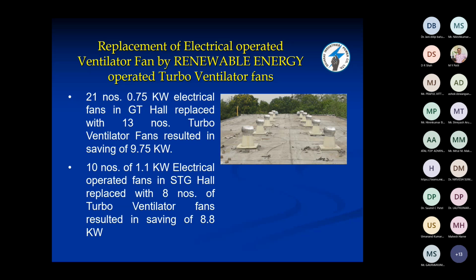A total of 21 numbers of 0.75 kilowatt electrical fans in the GT hall were replaced with 13 numbers of turbo ventilator fans, which has resulted in a saving of 9.75 kilowatt. You will consider that it is a very small saving, but when it is running 24 hours for all the year, when considered in terms of money, it is a very huge saving. And 10 numbers of 1.1 kilowatt electrically operated fans in the STG hall we have replaced with 8 numbers of turbo ventilator fans, resulting in a saving of 8.8 kilowatt.